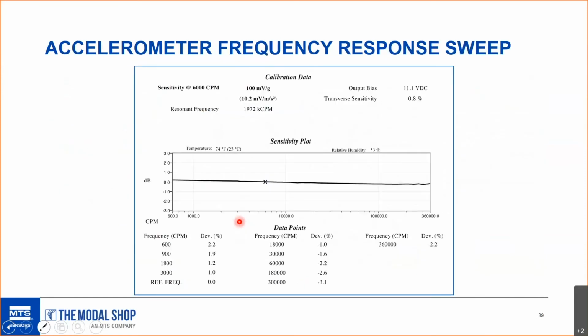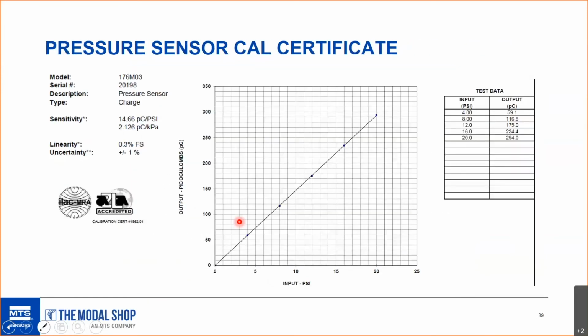Well, let me ask you something, Mike. Can you go back one? Okay. Can you do that plot from 1 to 5? Yes, we can. Good point. Absolutely. That's the characteristic, that's the ability of the 903 series calibrator. We have a low pressure level of 1 psi, and then it can be configured to stop at 10 psi or go up to 150.